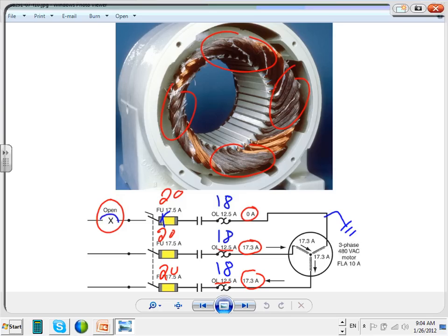I like these pictures because hopefully they bring it home. Single phasing creates an overload situation for you. Okay, and you see why these windings are burned, these two, the ones that we highlighted there, because they're taking 17.3, 17.3. This winding has 0, and that's why this part here is not burned. But who cares? You lost your motor. If half of the windings or even 1/3 of the windings are burned, you're dead.